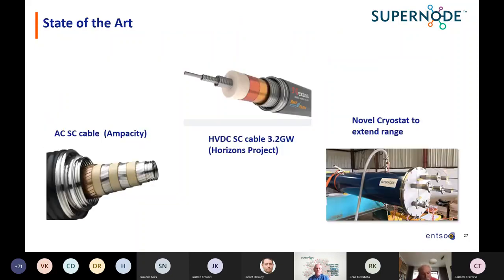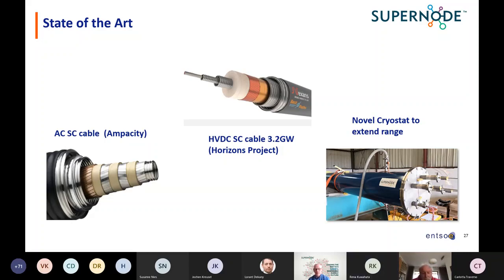What's the state of the art? On your left you'll see a Nexans cable used in the Ampacity project in Germany. It's an AC cable — three phase — with a cryogenic outer cryostat that keeps the superconductor cool. Liquid nitrogen passes through the center of the core and back through the annulus, keeping the whole thing cool and lossless. These cables are in the technology readiness ladder at TRL 8, or some would argue TRL 9.